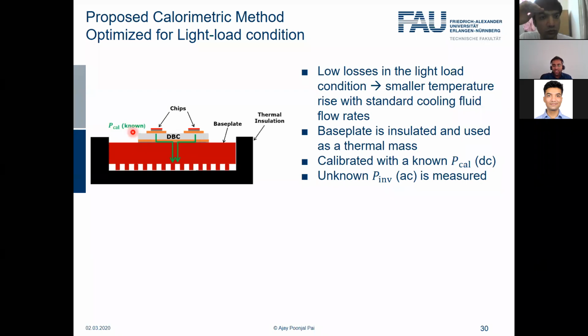So I inject DC power, which is known and calibrated, and then I see what is the temperature rise of the base plate for a known power. I do this at different points, so I have a calibrated curve now. Then I inject the unknown inverter power. I don't know what the power loss is, but because the rest of the system is the same, I can use the temperature rise to back calculate what was the injected power. This is the idea of this method.